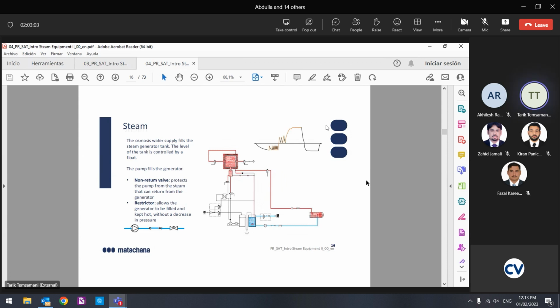First of all, we need to check the water is filling the steam generator. If it's not filled until the third sensor, the heating element will not turn on. So first of all, we need to check that. Then if the heating element is on, we need to check that the valve is open and steam is going to the jacket. If there is steam in the jacket, then the third part we need to check is the valve between the jacket and the chamber, as well as the return path, the feedback path. That is also quite important.